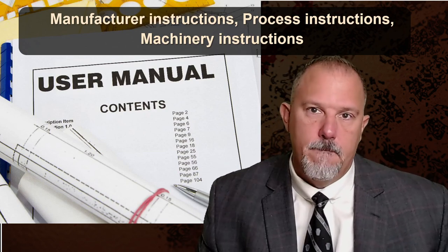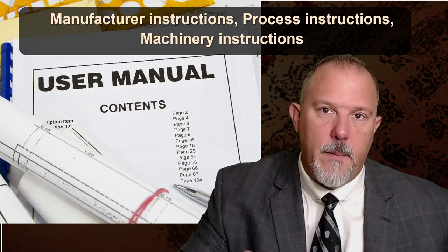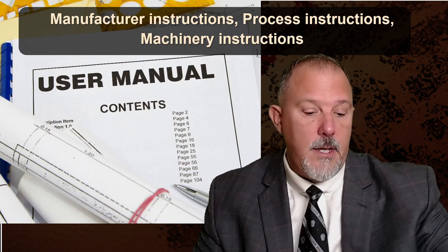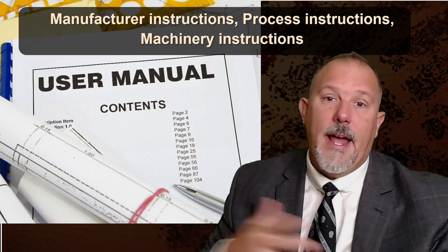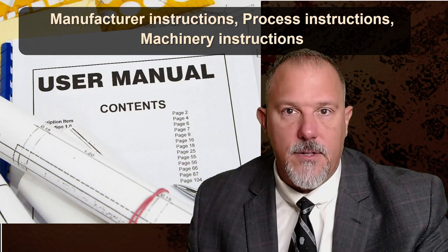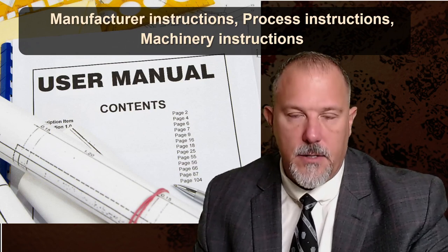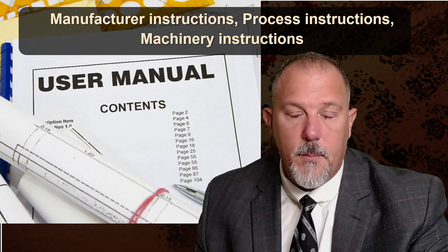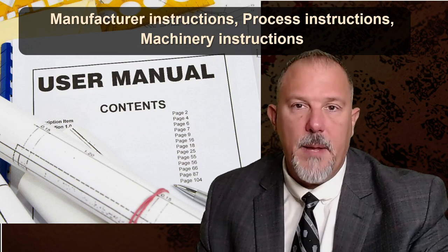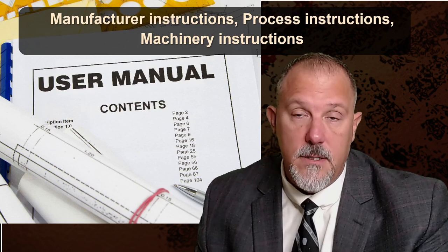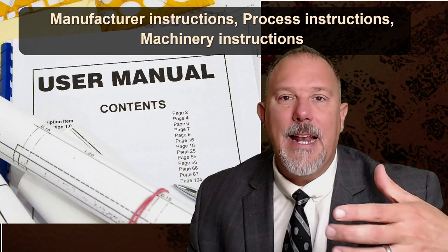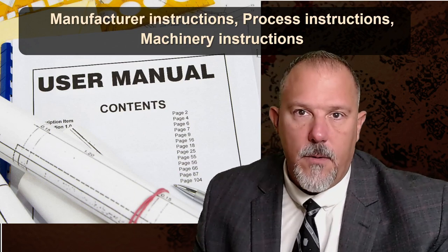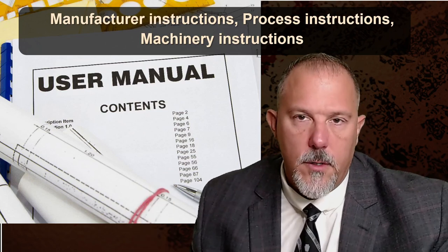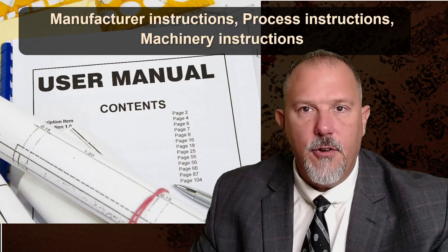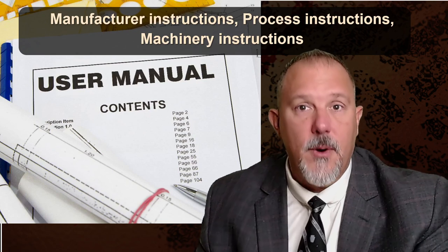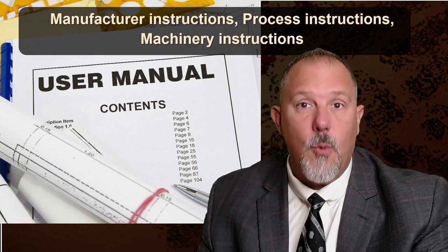My facility is not the same as your facility. The equipment I have and my processes aren't the same as your equipment and your processes in your facility. You need to be qualified. The qualified person will understand the hazards. And I say this: anytime you get training on a product, think about this. Anytime you get training on a product, the installation of a product, the maintenance of a product, whether it be a circuit breaker, fusible switch, panelboard, switchboard, a receptacle, for goodness sakes. Any training you get on any electrical product, on a light fixture, on a treadmill, on a motor, on a fan, any product that you interface with, the training you get on those products is a part of a 70E program of building the qualified person.